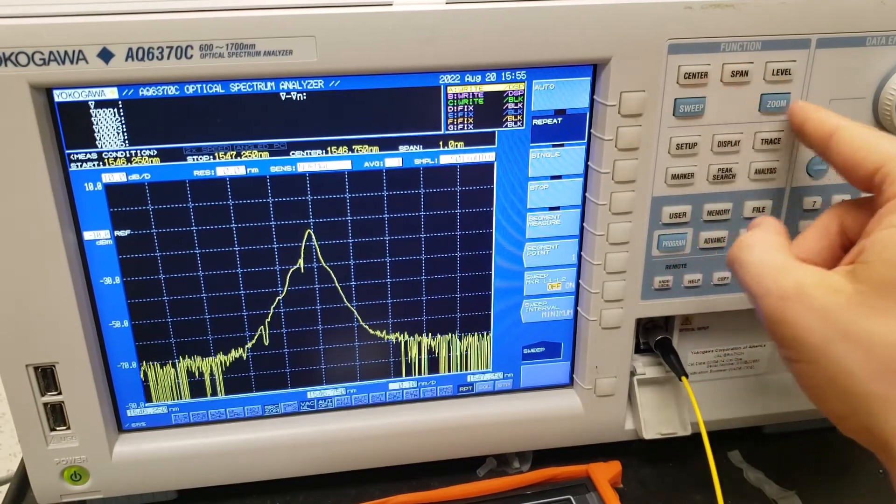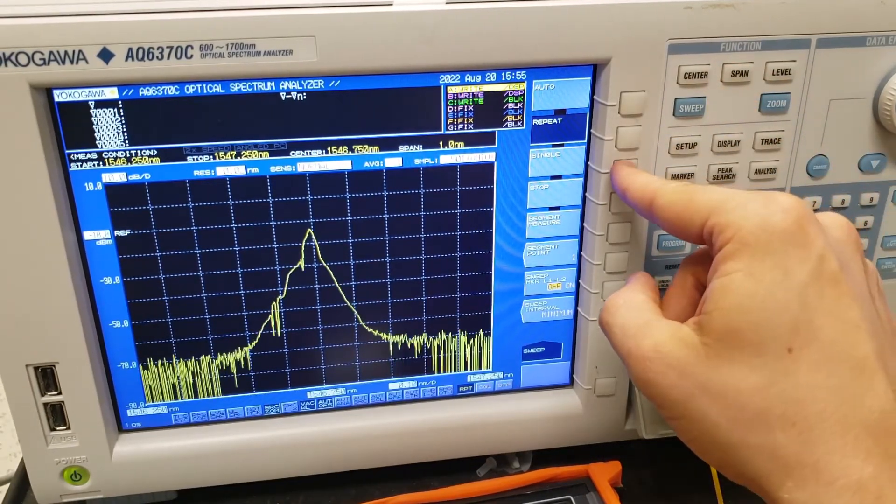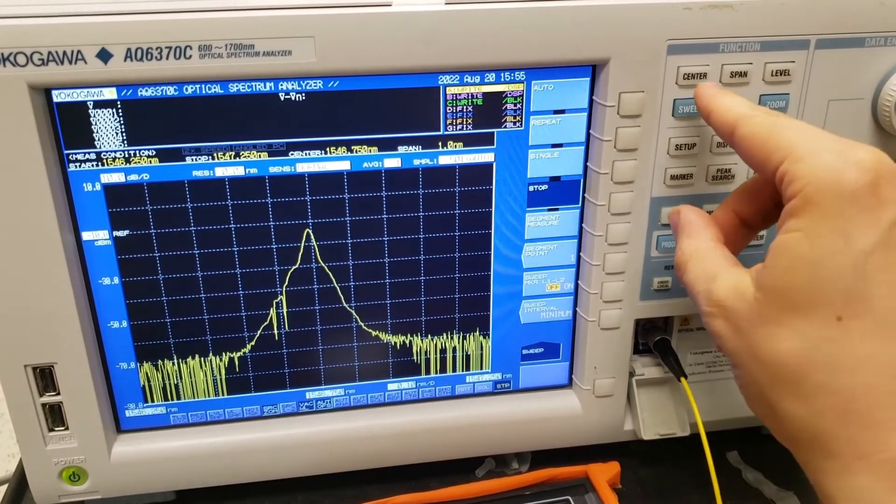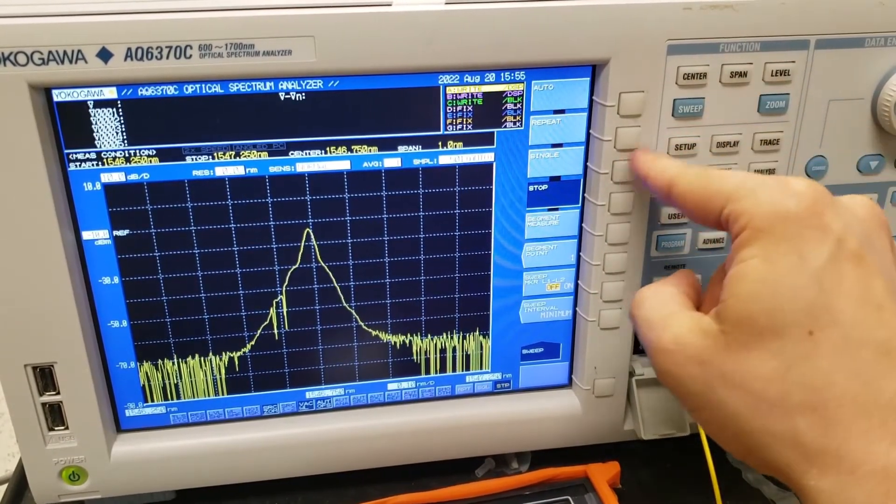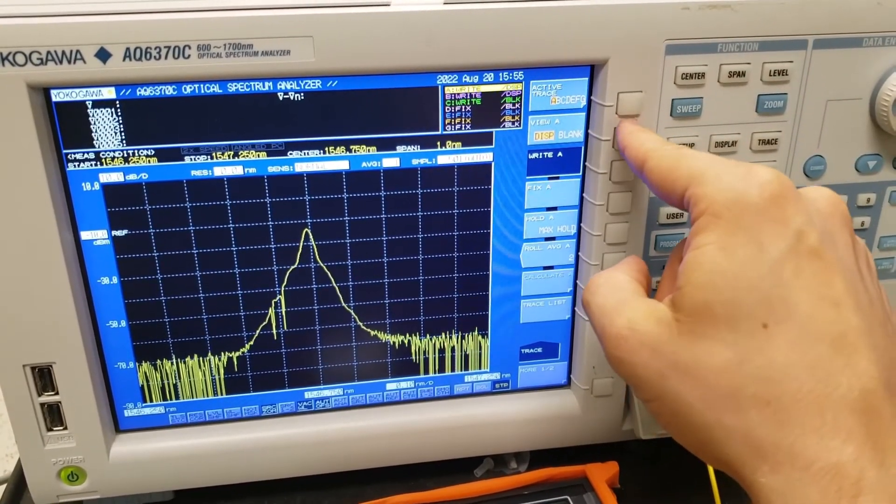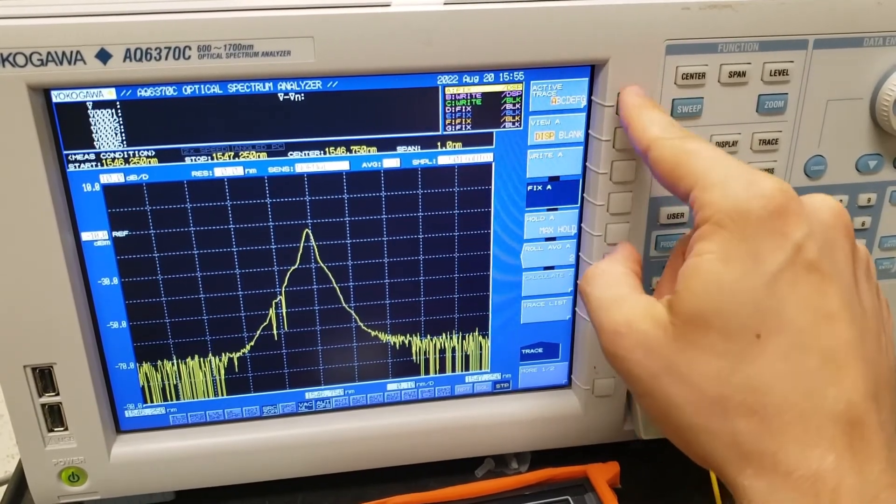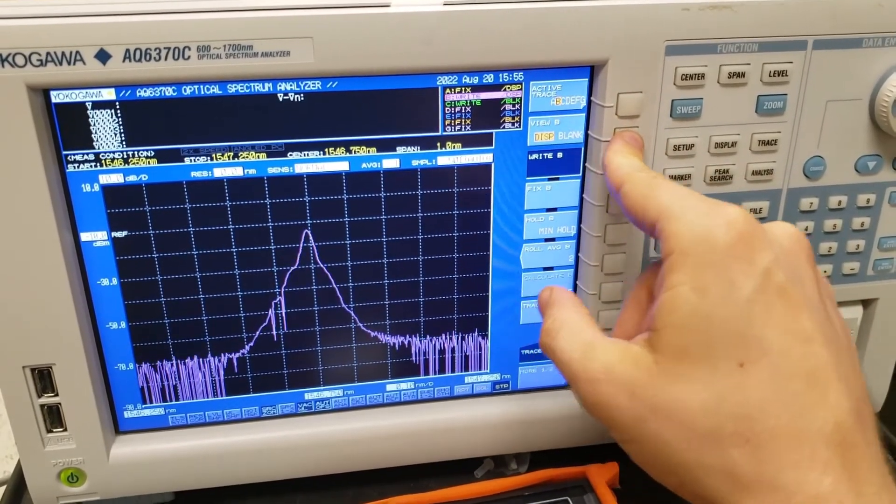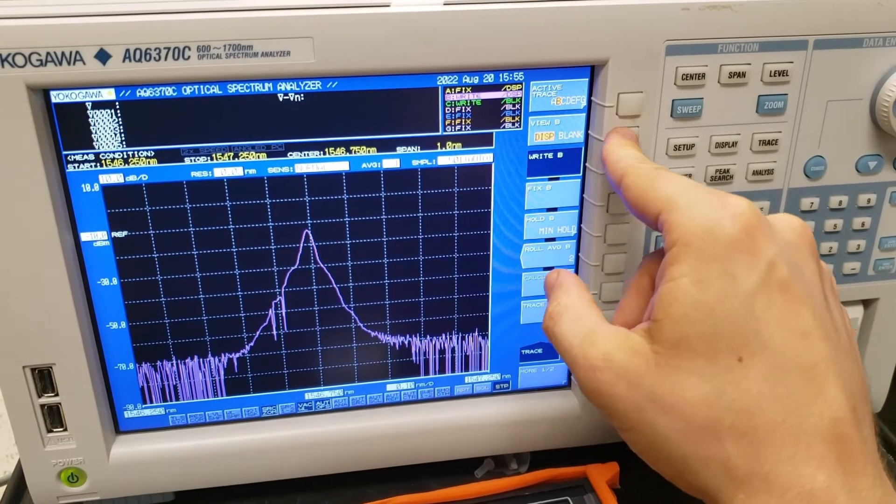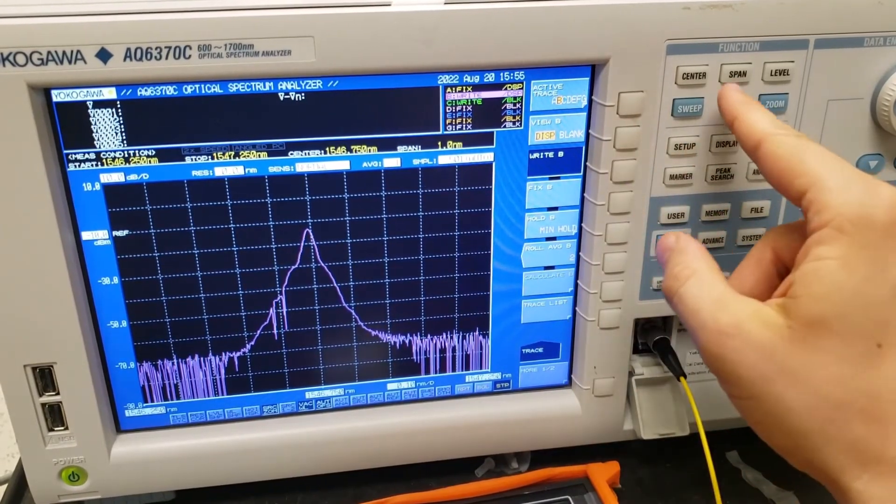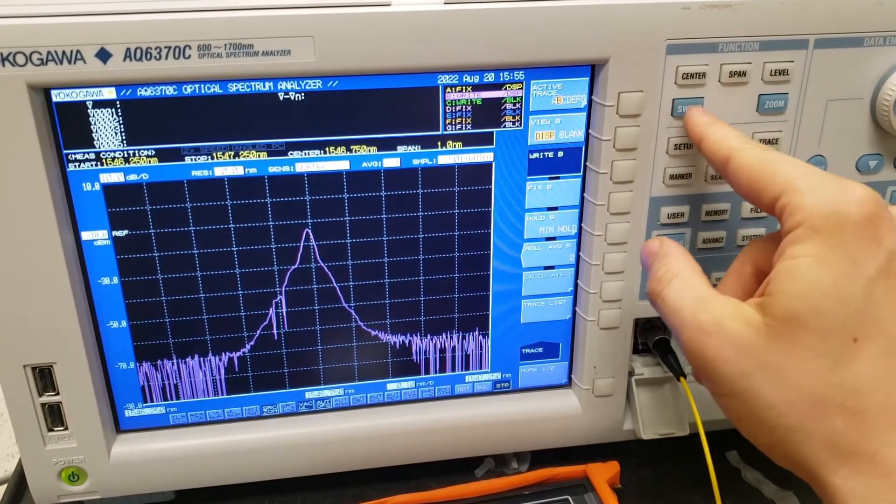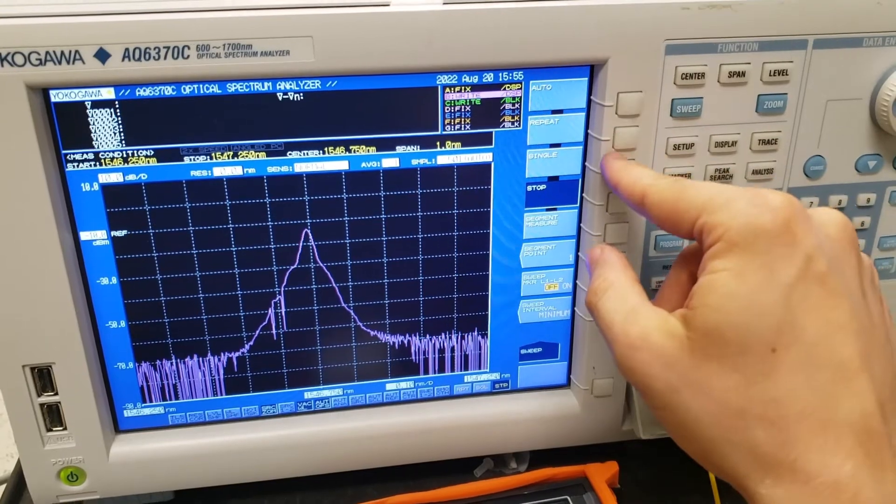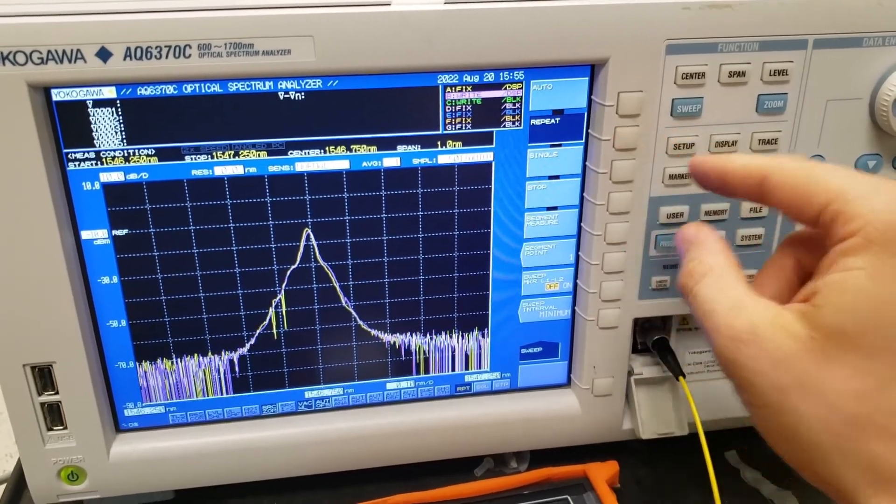Okay, so let's actually see what happens if we attenuate this a little bit. So let me press single here. And now we're going to go to the trace button, and we're going to fix trace A, and select trace B and set it to write and display. And then we can sweep, do another sweep, and repeat it.